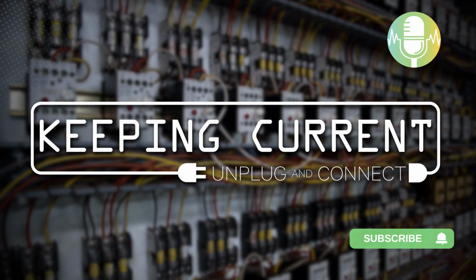One thing I got to see is how dynamic today's BESS inverters really are. We installed a 1.5 kilowatt system at both locations, and during commissioning, something that jumped out to me is the bidirectional inverter, right? These inverters can charge and discharge, which we know from the previous segment. But what's really interesting is how fast they can actually change, going from charging 1.5 kilowatt hours to discharging 1.5 kilowatt hours in literally seconds. The response time of these inverters is just phenomenal.